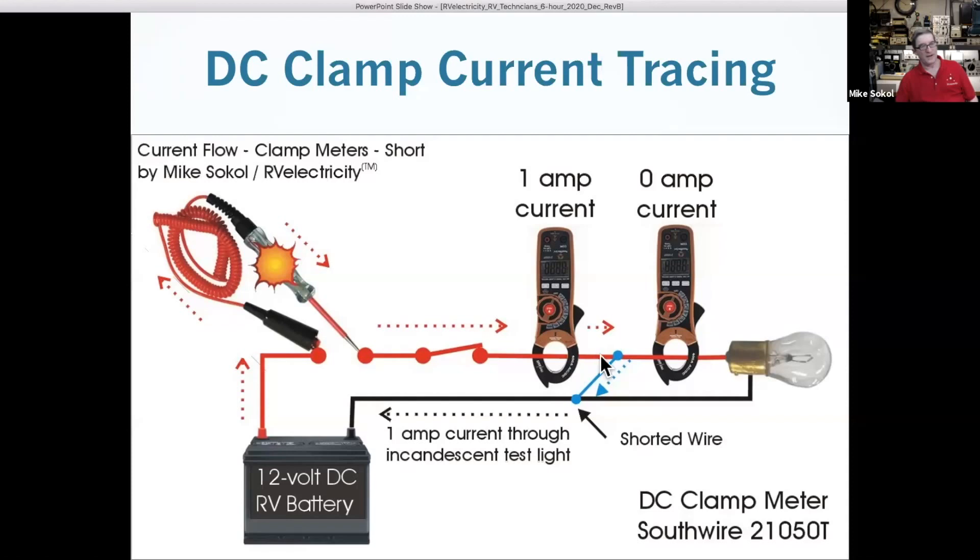I had one guy that had a short circuit in his DC wiring for two or three years and none of the technicians could find it. I showed this to him. In under a half an hour, he went through and found out the current got as far as the ceiling and didn't get to the other side.